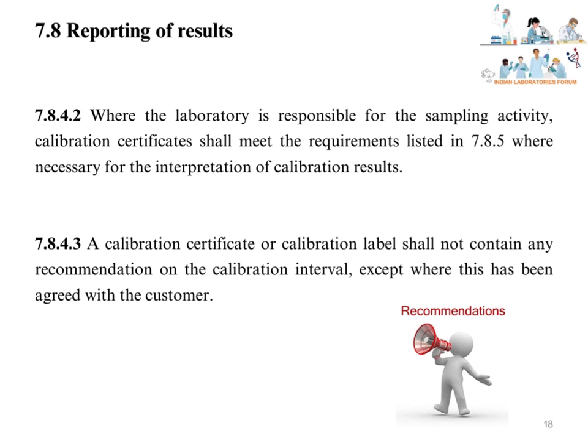Where the laboratory is responsible for the sampling activity, calibration certificates shall meet the requirements listed in 7.8.5, reporting sampling, specific requirements, where necessary for the interpretation of calibration results. Specific requirements for reporting of sampling activities are defined in Clause 7.8.5 of the standard. The laboratory has to comply with the requirements of that specific clause when reporting the sampling activity. A calibration certificate or calibration label shall not contain any recommendation on the calibration interval, except where this has been agreed with the customer. The laboratory should not give a calibration due date voluntarily. The laboratory can only report the due dates when those are agreed with customers.